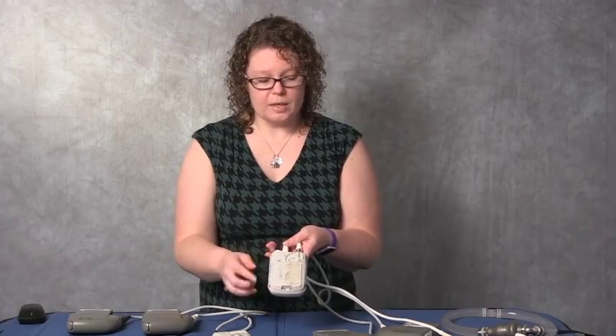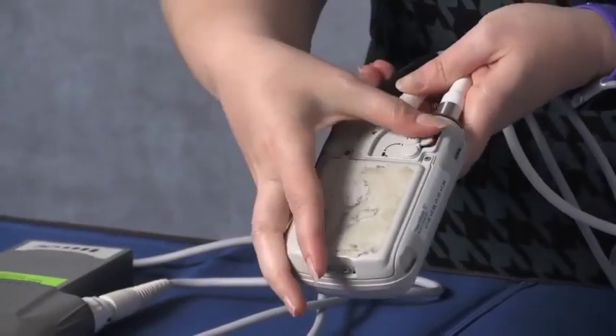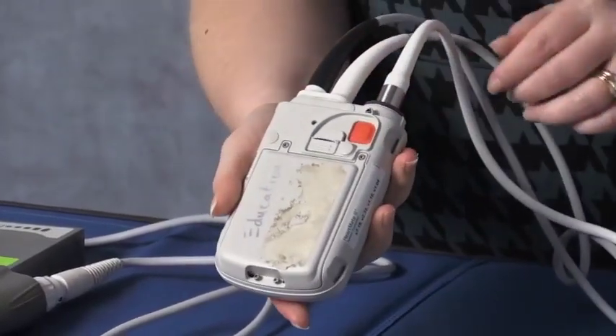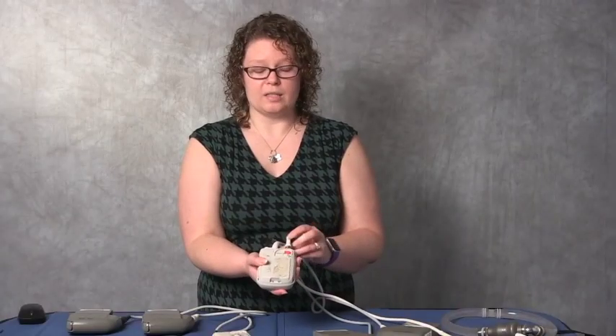Okay, now we're all set. One of the safety features of the HeartMate 2 is this trap door, and this trap door protects the red button, which must be pressed and held down in order to remove the driveline from the controller itself.